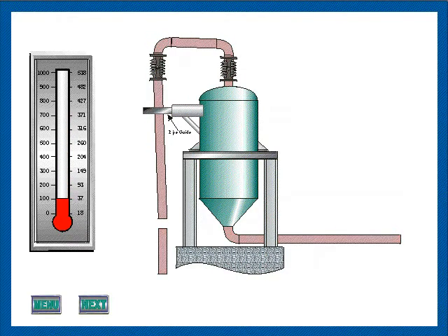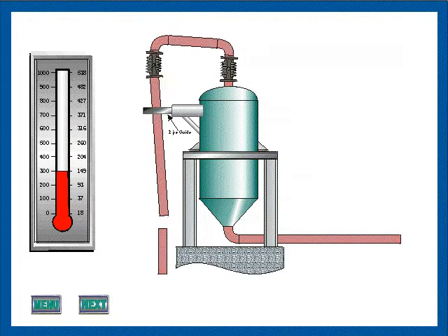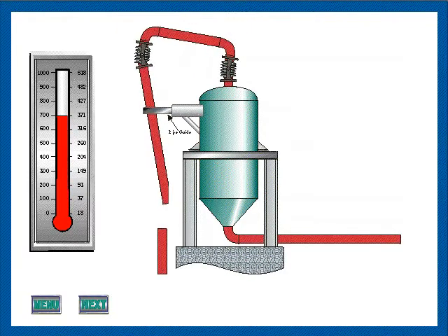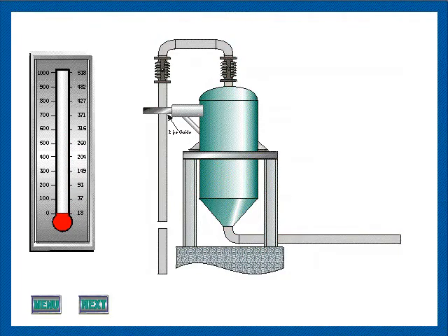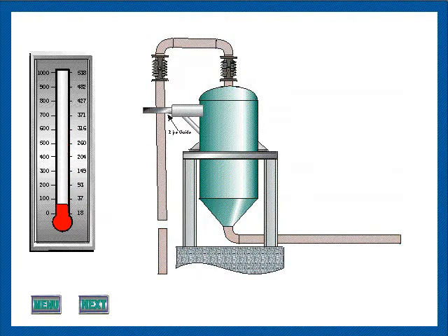By utilizing the rigidity of the hinges, a substantial portion of the weight of the upper horizontal leg may also be carried on these lower supports. It should be noted that the sliding supports nearest the vertical leg must be designed to resist the force required to deflect the piping.